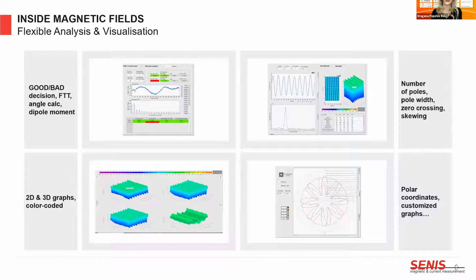Here are some visualization graphs of the measured magnetic field data. The software generates a 3D map of the magnetic field, counts the number of poles, calculates pole width for multiple magnets and rotors, detects zero crossing, measures magnetic angle, and much more.